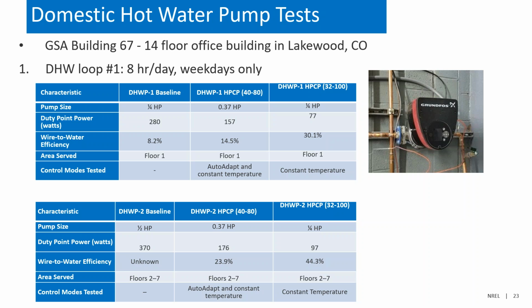And then again, about halfway through the demonstration, we installed this 32-100, which is a quarter horsepower pump. And I think one of the challenges in sizing these small pumps is you don't have differential pressure ports on the pumps themselves. So it's hard to know exactly what the flow rate is through the system. We do go through in the report a methodology to help analyze if the flow rates are appropriate and if you can install a smaller pump. But just one thing to keep in mind, it is challenging with these smaller pumps of really knowing what the flow rates are.